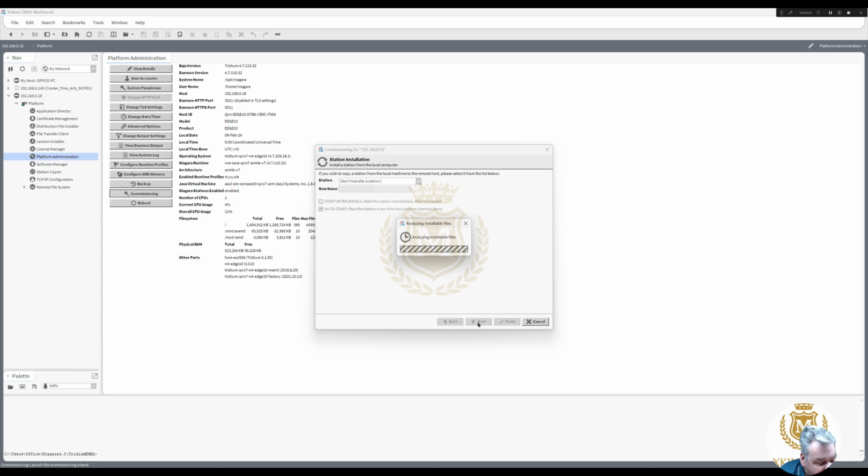You really need a station, and we really should have just made a quick station, because it will only transfer the palettes across that are required for the station. So if you're using logic blocks, it would take across the kitControl palette. Because I'm not using a station, it's not going to take anything across. Looking at the drawing, there's no networks here.